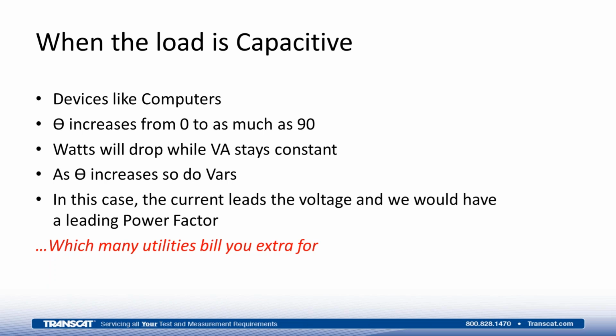Leading power factor is even more difficult for utilities to overcome, and again, they would have the potential ability to bill you for that. Now, it's not too common in the industry. In the past, if you had an inductive load with a lot of motors, either you might in your facility have something referred to as a capacitor bank that is supposedly put in there to help you, or the utility would hang capacitors on the distribution lines coming to your facility. And they're done specifically to try to offset the VAR loading that your facility would present. And if these capacitors are working properly, they would only offset as much inductive load as you were putting onto the system, and we would never lead to this situation of a leading due to those capacitive loading.